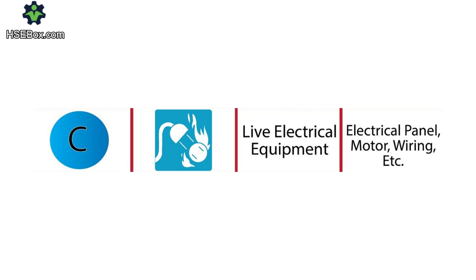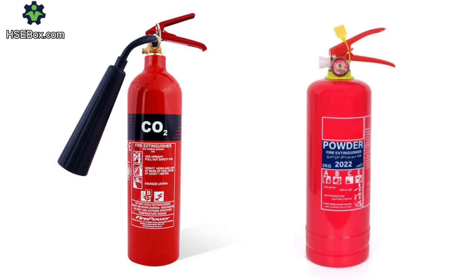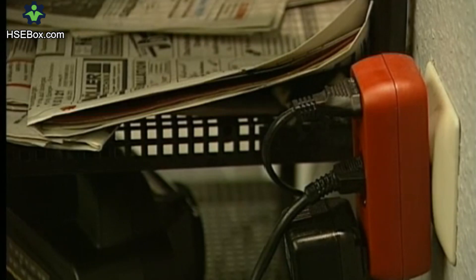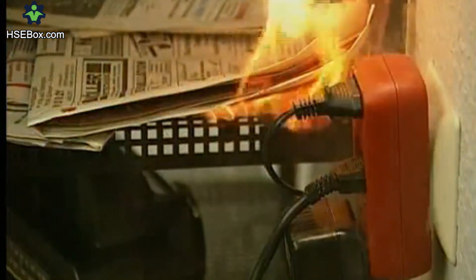Water conducts electricity and can lead to electrocution if sprayed on electrical fires. For class C fires, carbon dioxide or dry powder extinguishers are your best bet — these extinguishers eliminate oxygen without risking electric shock. Think about an electrical short circuit that sparks a fire in a server room; that's a typical class C fire scenario.